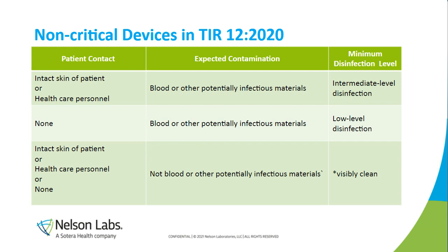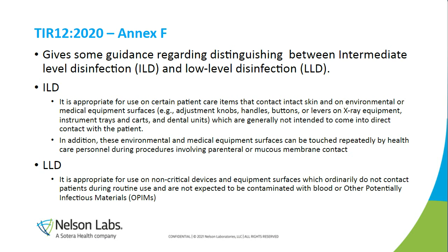Annex F in TIR12 also offers further guidance on when an intermediate level disinfection or a low level disinfection should be performed, with suggestions based off of parts of devices and medical equipment that receive high levels of touch and interaction during use. But there's still some gray area as to when intermediate or low-level disinfection should be performed, but now we can see that there are some visible edges between the shades of gray as to what should be performed on which devices.